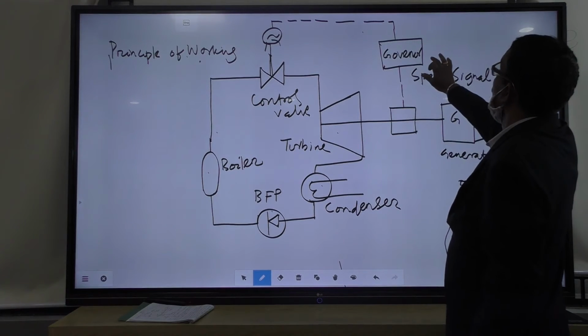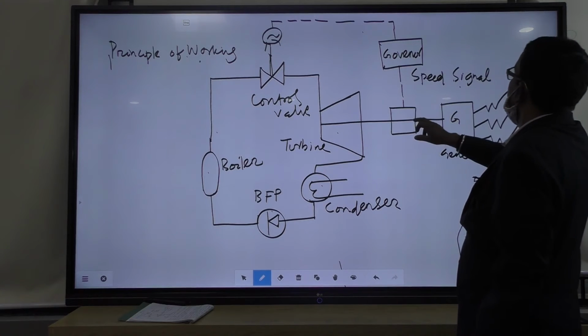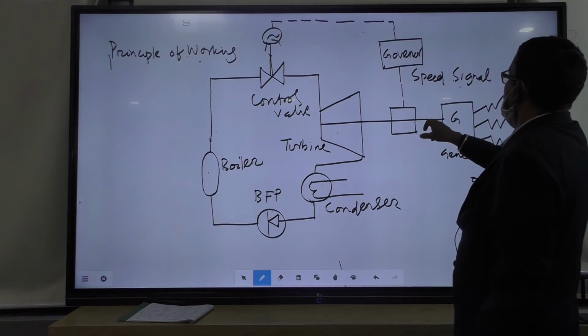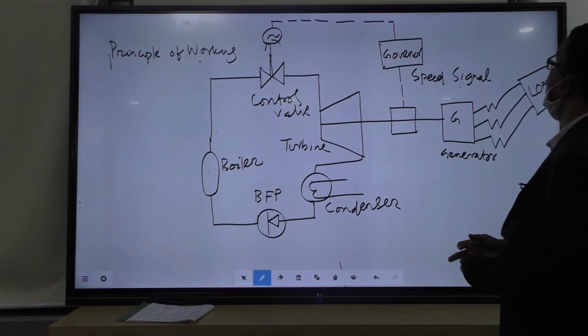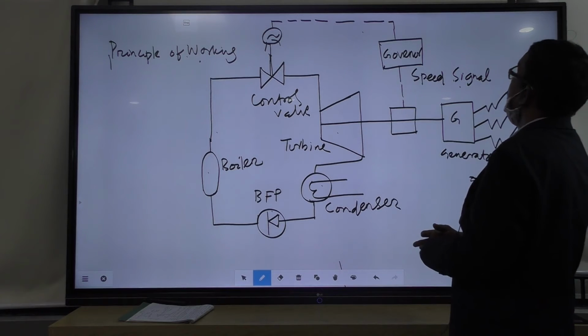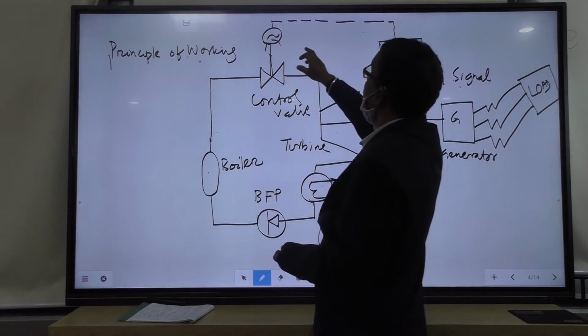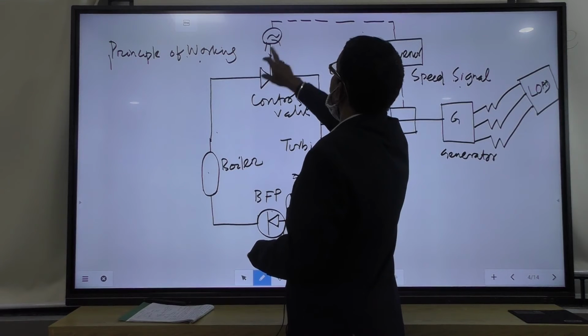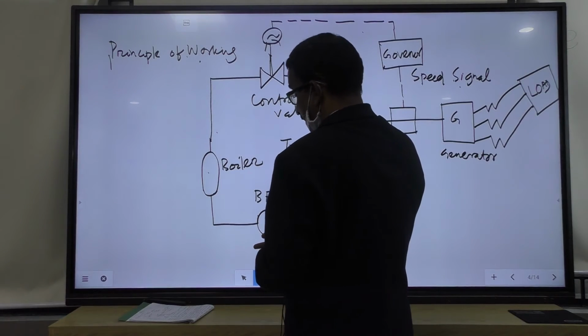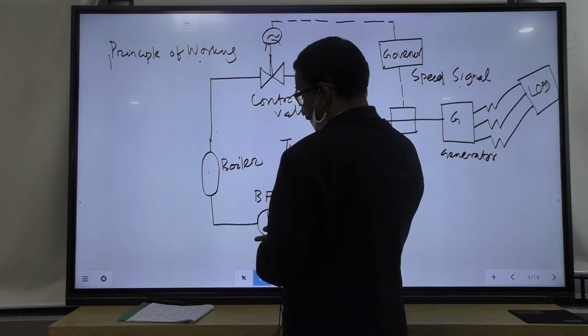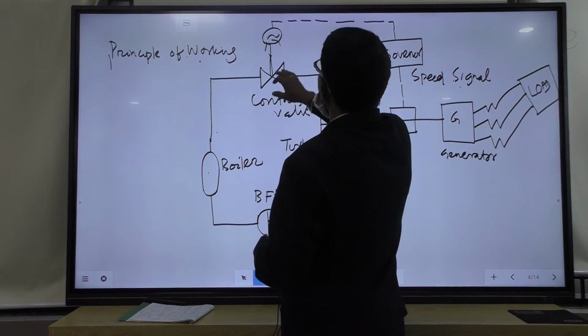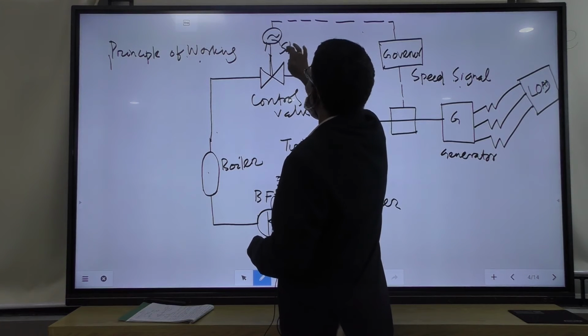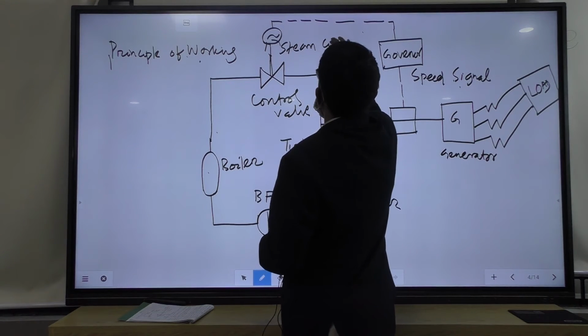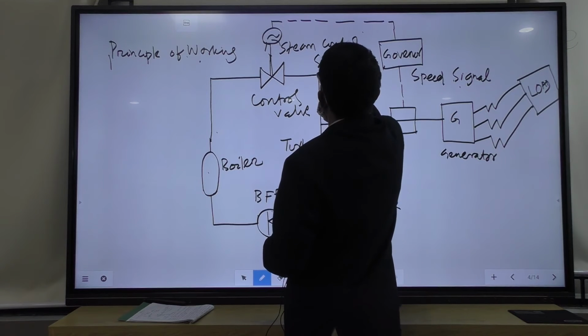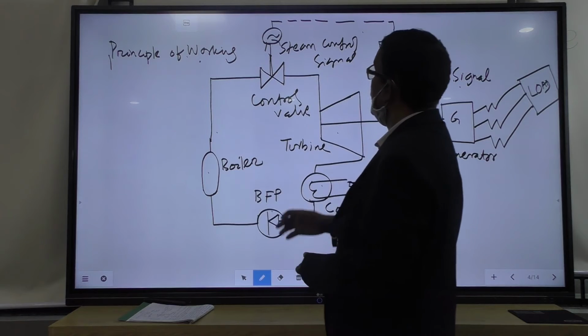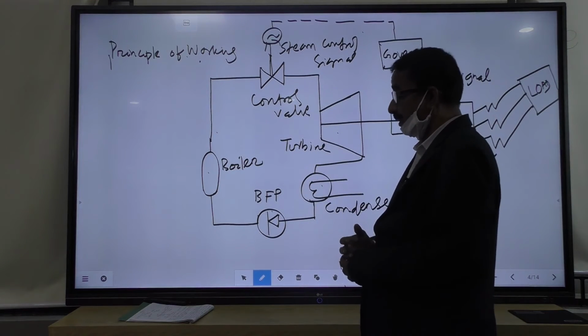So, here this governor is located and this is the signal coming from the turbine shaft, the speed signal, how much speed the turbine is rotating at, and the valve is opened by the governor. Steam control signals. This will give the signals to the control valve, so that the valve will open or close depending upon the demand.